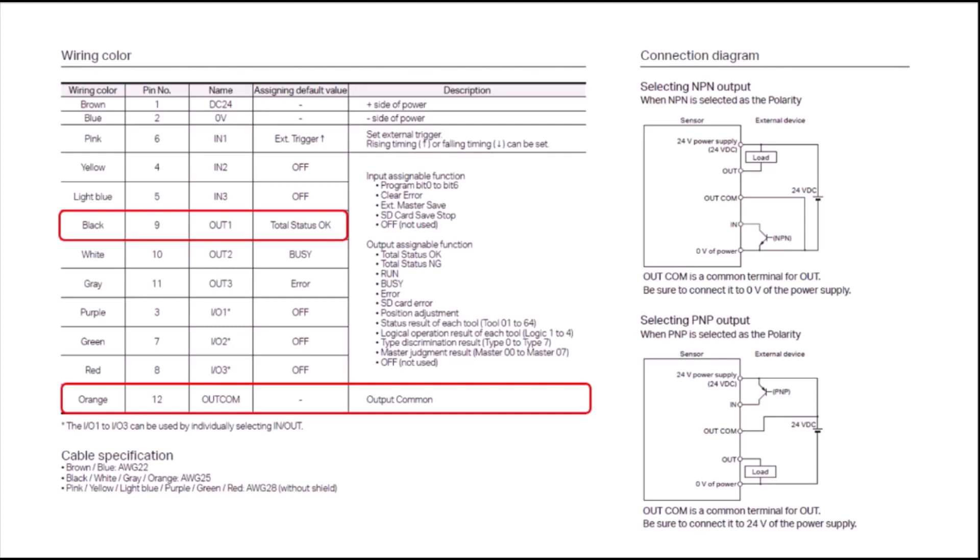We also want to note the orange wire, which is our output common. This output common is required in order for your outputs to work correctly. So if you are having some issues, always check the orange wire connection.